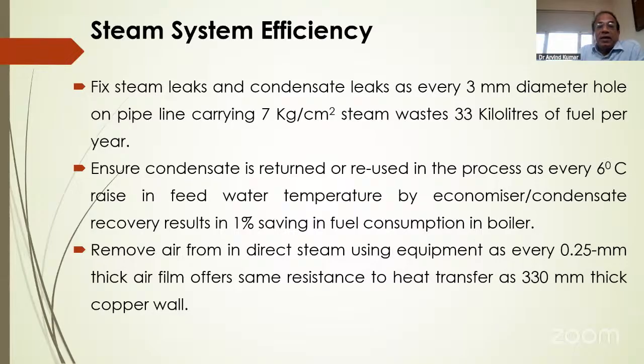Fix steam leaks and condensate leaks. Every 3 mm diameter hole on a pipeline carrying 7 kg per centimeter square steam wastes 33 kiloliters of fuel per year. If there is steam in a pipeline at a pressure of 7 kg per centimeter square and there is a 3 mm hole, that hole tends to waste 33 kiloliters of fuel per year.